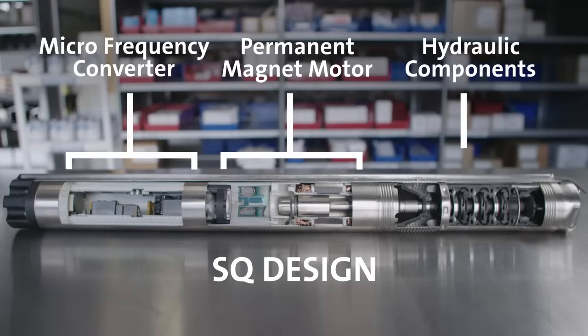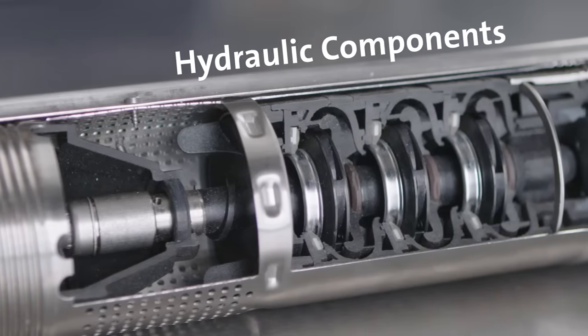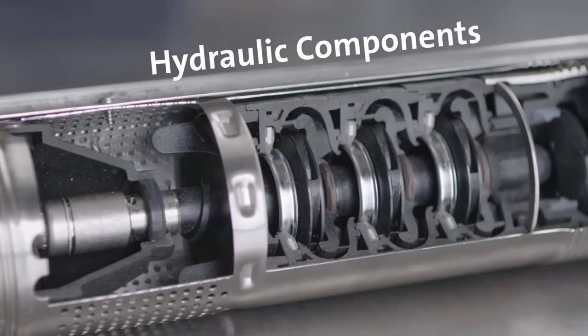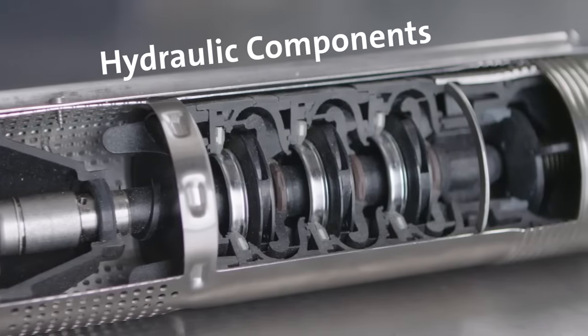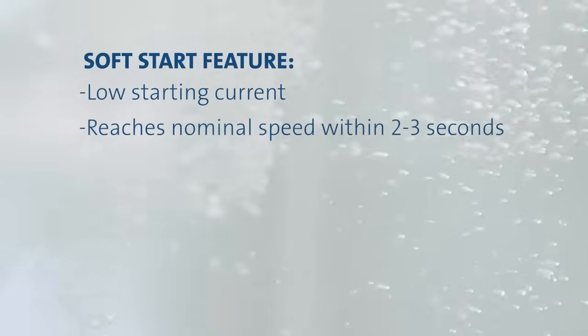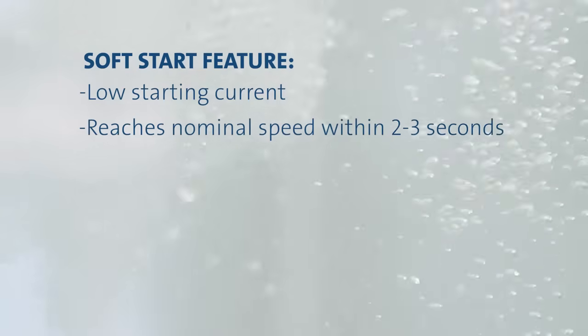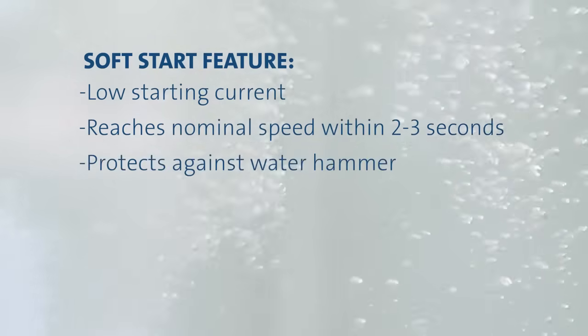The hydraulic components of the SQ pump are specifically designed for high-speed operation, optimizing water production. The floating impellers feature tungsten carbide ceramic bearings to ensure high wear resistance to sand and prolong the pump's life. Grundfos SQ includes a soft start feature which provides low starting current to reduce electrical load. The motor reaches nominal speed and current draw two to three seconds after start-up through a smooth and steady acceleration, protecting against water hammer.